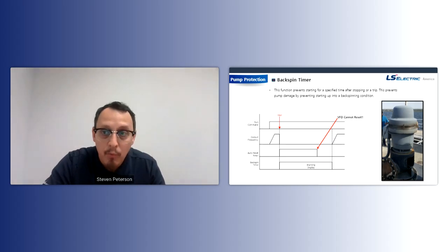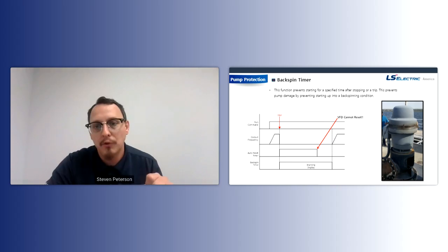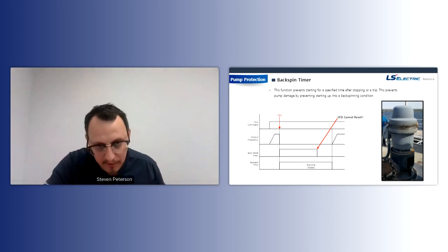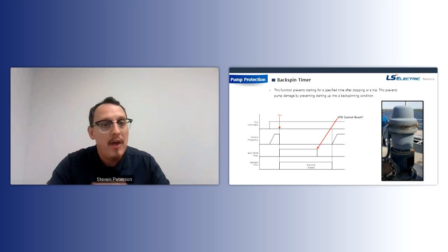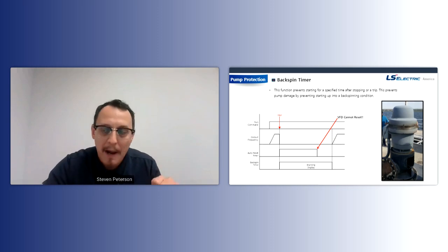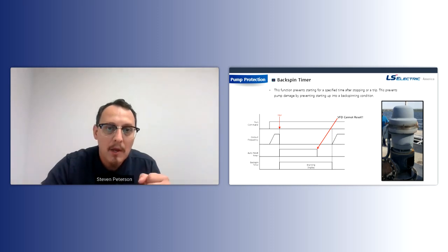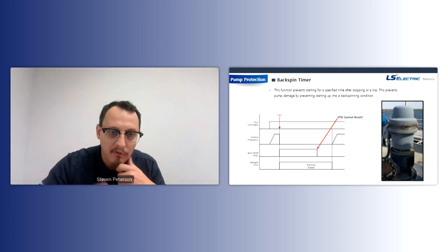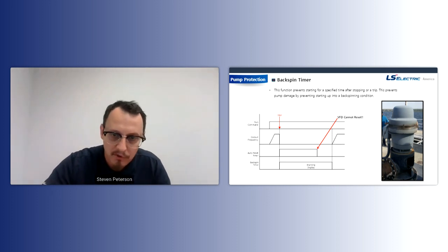We recently improved this, so that the timer keeps going with the real-time clock, even if you lose power. So somebody shuts off power to the drive and then powers it back on, and that backspin timer keeps going even with power off. So there's pretty much no way you can damage your pump as you set up this parameter. So this is another great feature.